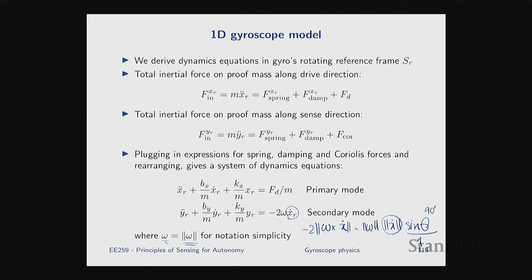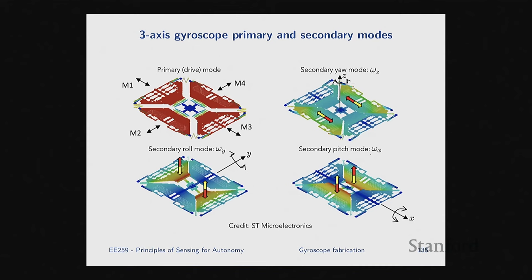this last picture we looked at. This one is very dependent on the architecture of the device, but for this one specifically, if we go back to, let me do it on the iPad here, how yaw affects what kind of Coriolis acceleration it generates on the two masses, you would see that from yaw, the two masses are going to experience Coriolis acceleration in different directions, right? And that's why these arrows are colored, because the reds are pointing to opposite directions. As you apply angular velocity, depending on the direction of your omega, one of the masses is going to experience a Coriolis acceleration in, say, the northwest direction. The other one is going to experience it in the southeast direction or something like that, if it makes sense. So the two masses are going to go in opposite directions.